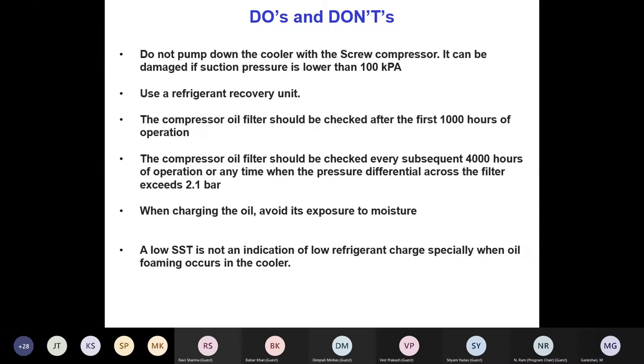Oil filters: manufacturers always recommend that after the first 1,000 hours you immediately clean or remove them, because after flushing some debris will come. Once you do that, in future just watch the pressure drop between the inlet and outlet of the filters. If it is more than the recommendation, replace it; otherwise you can let it be. When changing the oil, avoid exposure to moisture because these are all hygroscopic oils, so be very careful. Also, low SST is not an indication of low refrigerant charge, especially when oil foaming occurs inside the cooler. I was telling you, when there is foaming inside the cooler oil, we need to really look for that.